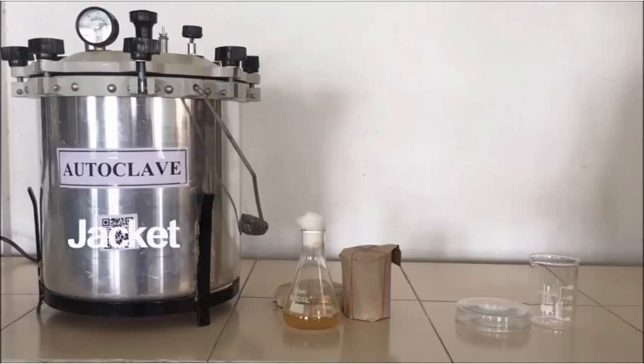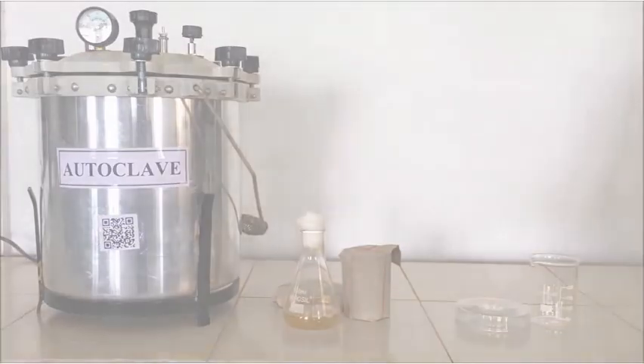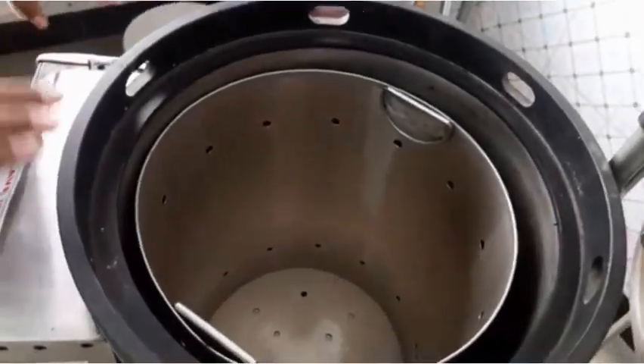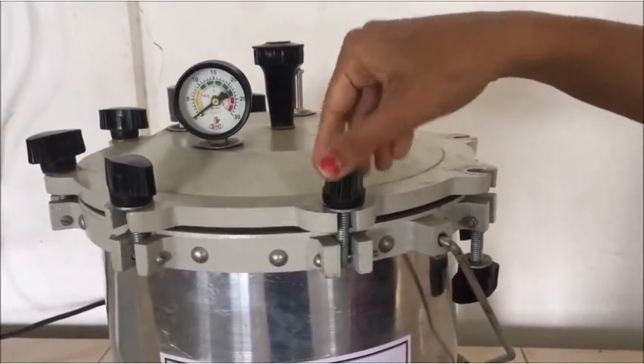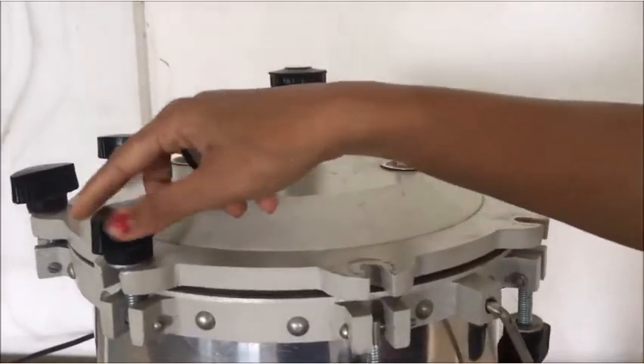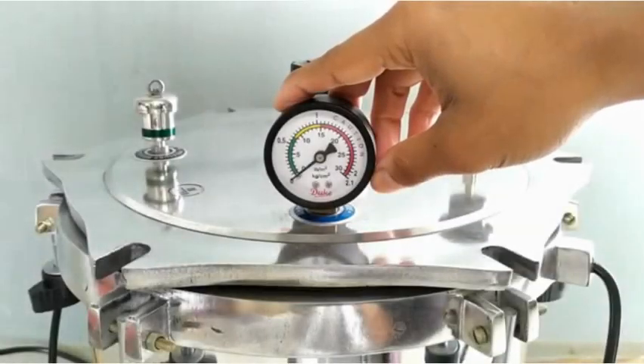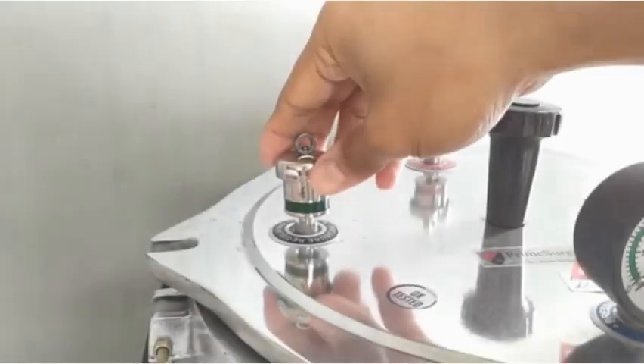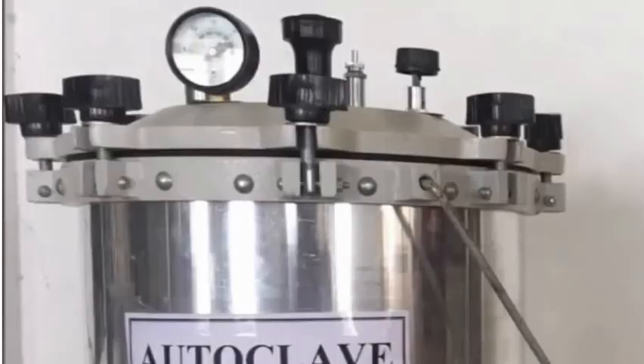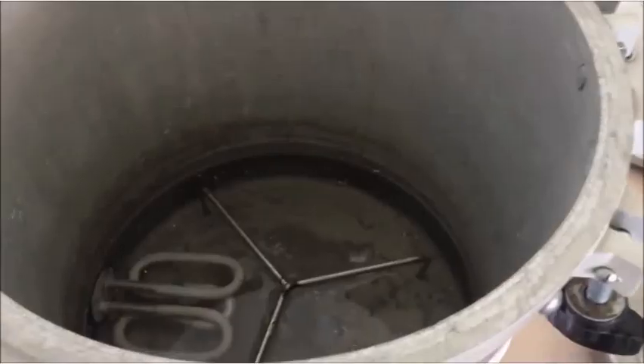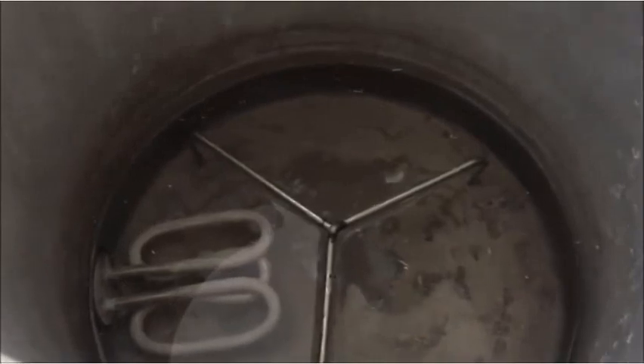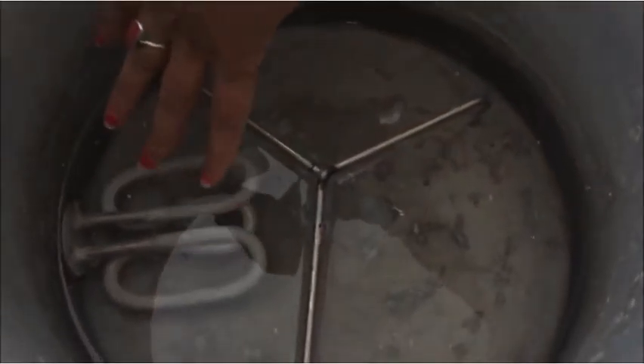An autoclave is a cylindrical vessel made of stainless steel. There is an outer layer called the jacket, and inside it is the perforated basket. There is an upper lid, also made of steel, fitted with many different things. A cover is tightly closed with the help of a gasket, and attached to the cover are the pressure gauge, the exhaust valve, and a pressure control valve. Since an autoclave works at very high pressure, safety valves should be attached so that accidents can be avoided. At the base, inside, you will find a heating coil, and that heating coil has to be submerged in distilled water.